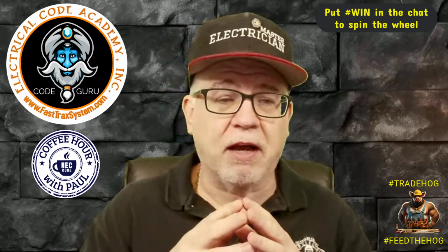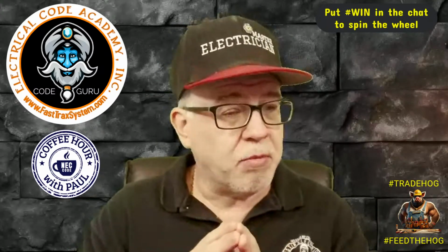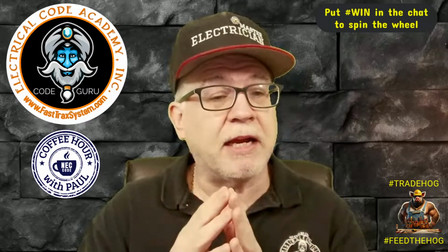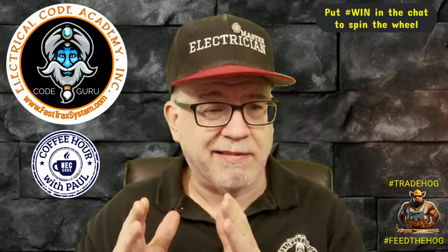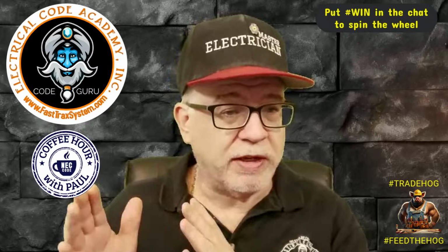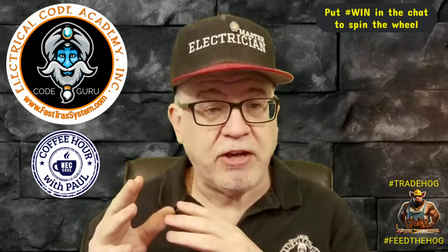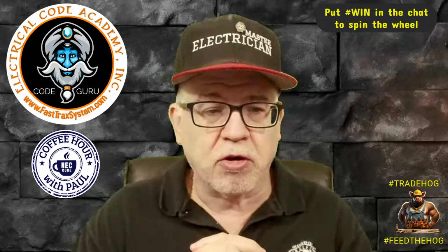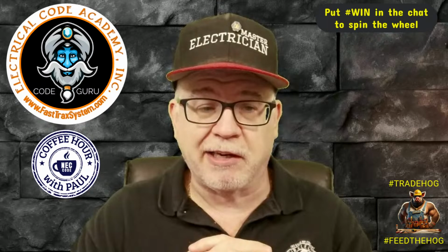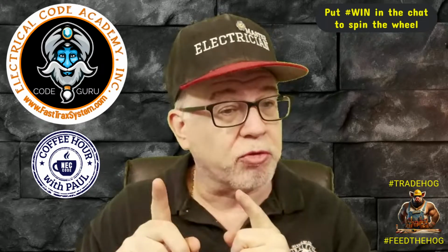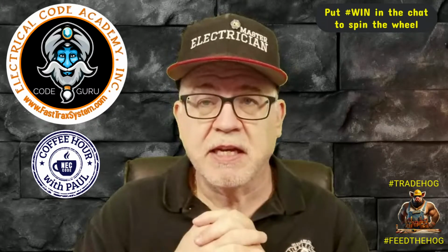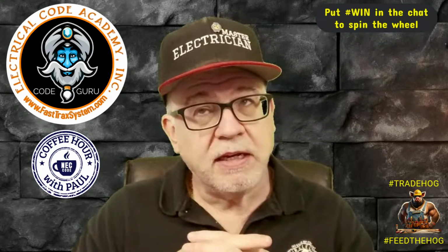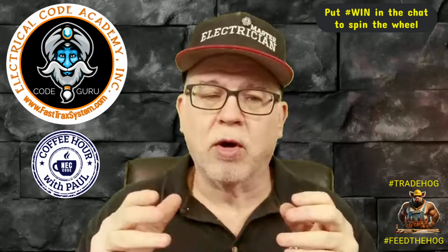Now, why do we parallel? We parallel because we're trying to get more ampacity. We're not paralleling equipment grounds because of that, okay? The code just says what we do. They connect them all together in a parallel nature. But when we parallel ungrounded conductors and grounded conductors, and we say grounded, we're also talking neutrals in most cases. Not all cases, but most cases. We're paralleling in order to get more capacity.